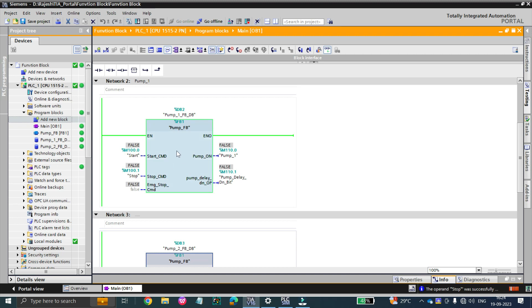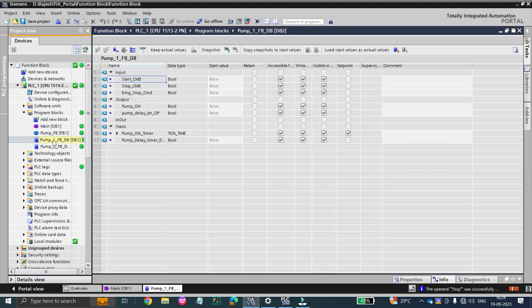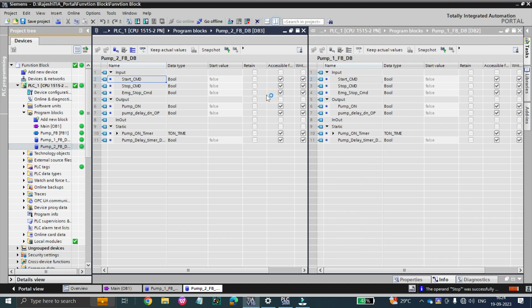It gets created as pump one FBDB, pump two FBDB, and so on. But in a function, that doesn't happen — functions don't have their own memory, so they don't create any DB or memory values. Let me give you the example: this is pump one FBDB and this is pump two FBDB. In the main block, let me go online.